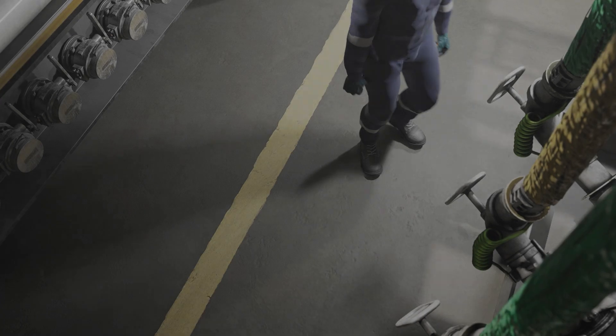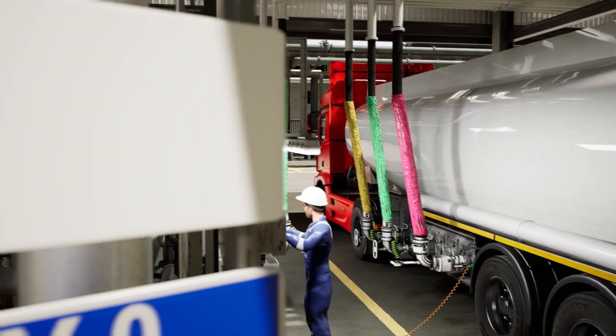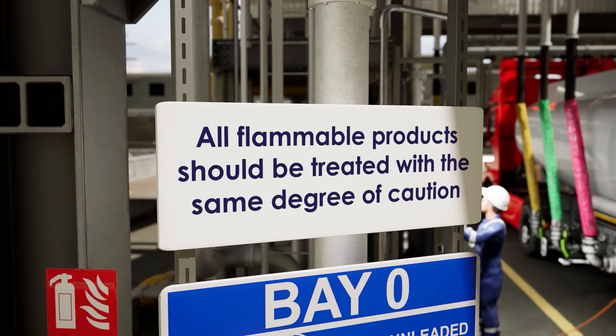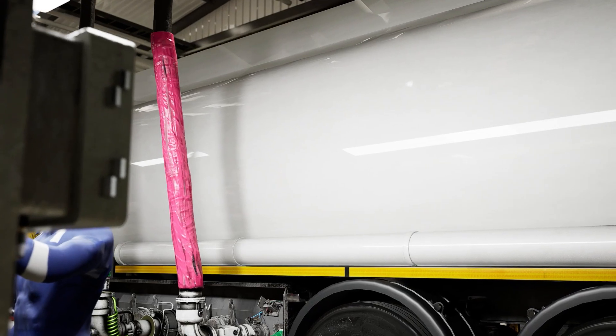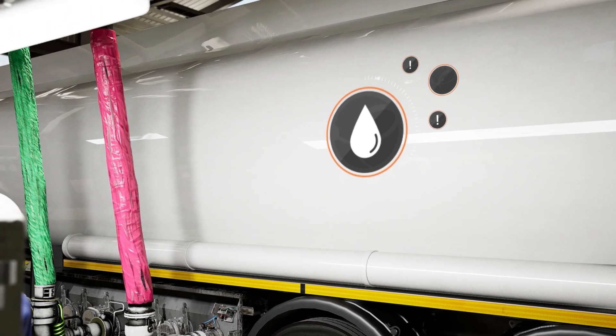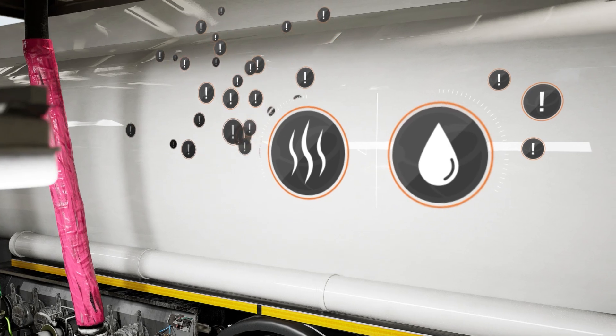Of course, this means that some products are more hazardous than others. But as switching products between containers is a common occurrence, all flammable products should be treated with the same degree of caution. For example, a product such as diesel poses little risk in itself, but when being switch-loaded with gasoline, it's probable that the vapor in the container will pass through a hazardous phase.